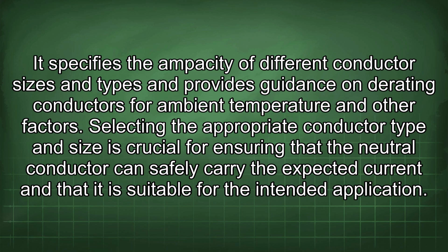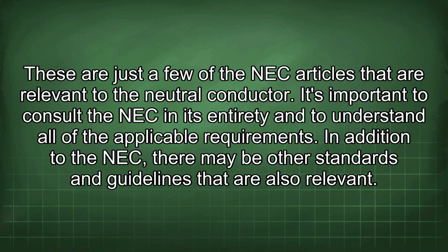It specifies the ampacity of different conductor sizes and types and provides guidance on derating conductors for ambient temperature and other factors. Selecting the appropriate conductor type and size is crucial for ensuring that the neutral conductor can safely carry the expected current and that it is suitable for the intended application. These are just a few of the NEC articles that are relevant to the neutral conductor.